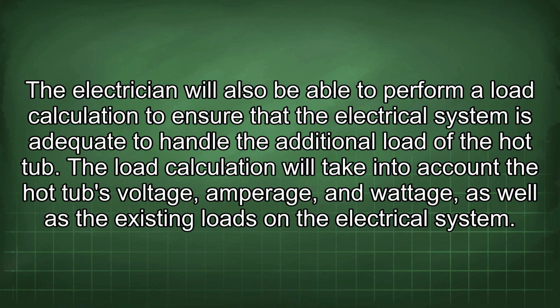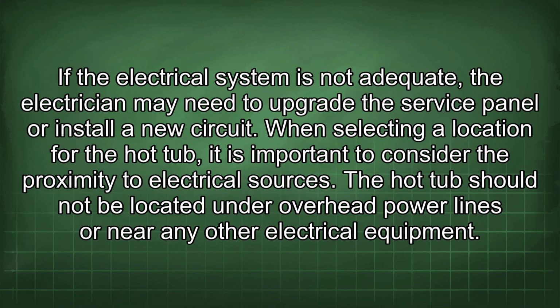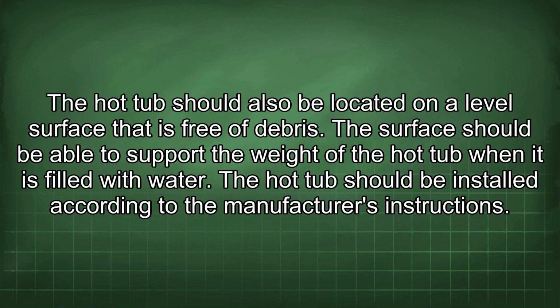The load calculation will take into account the hot tub's voltage, amperage, and wattage, as well as the existing loads on the electrical system. If the electrical system is not adequate, the electrician may need to upgrade the service panel or install a new circuit. When selecting a location for the hot tub, it is important to consider the proximity to electrical sources. The hot tub should not be located under overhead power lines or near any other electrical equipment. The hot tub should also be located on a level surface that is free of debris. The surface should be able to support the weight of the hot tub when it is filled with water.